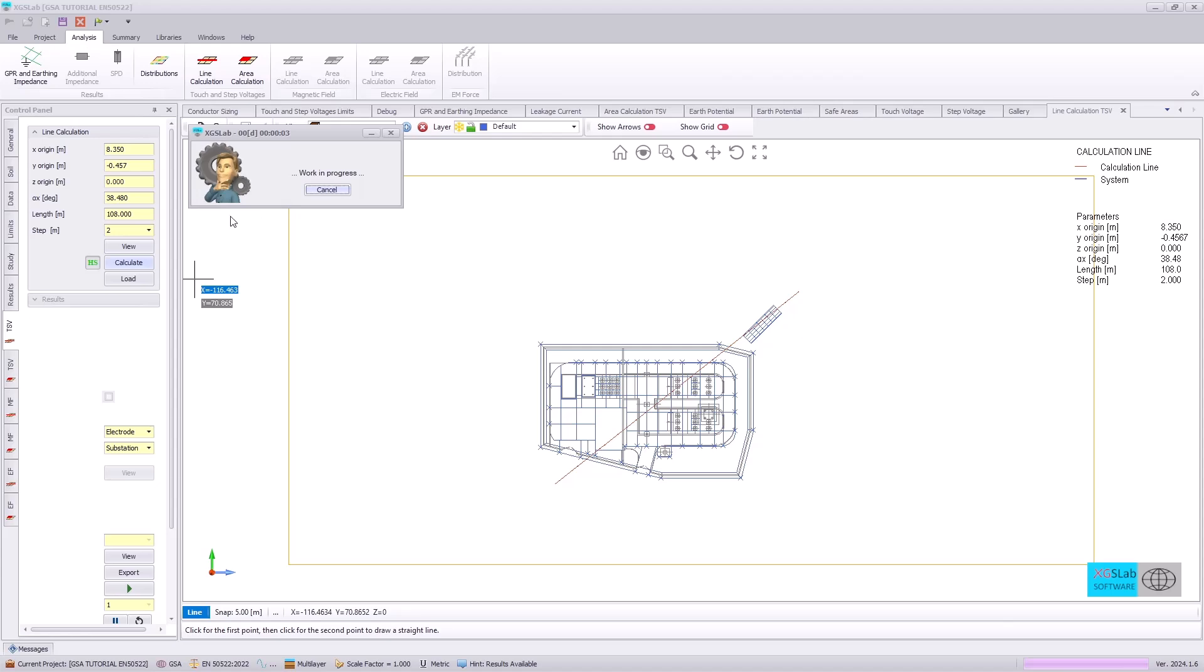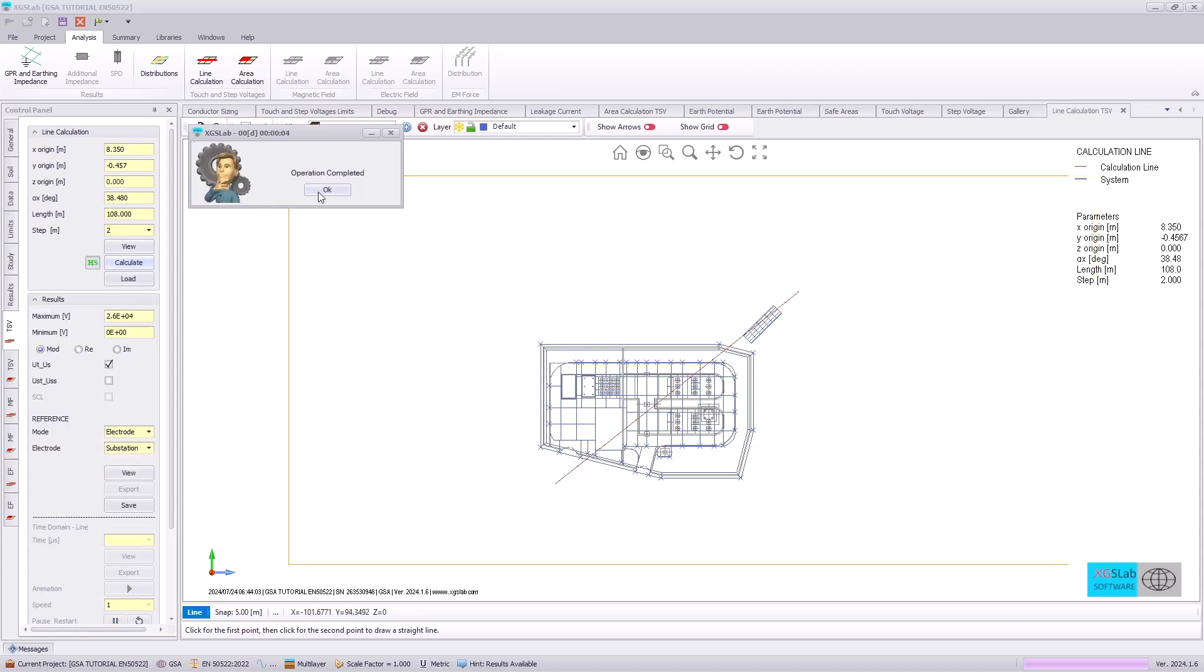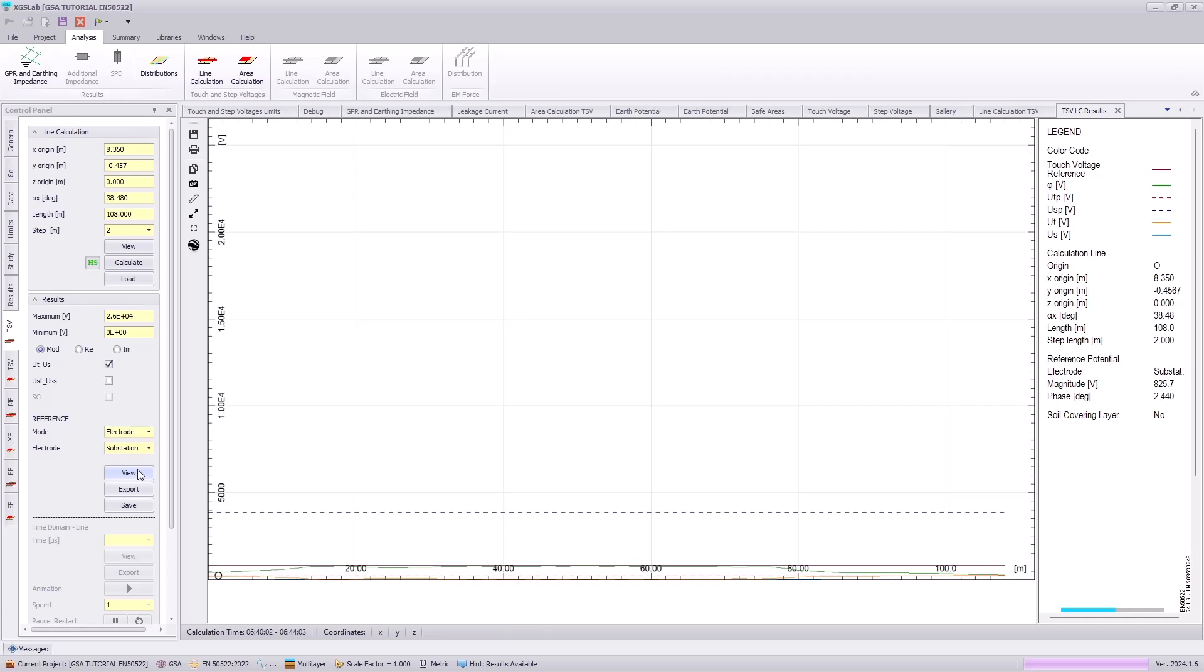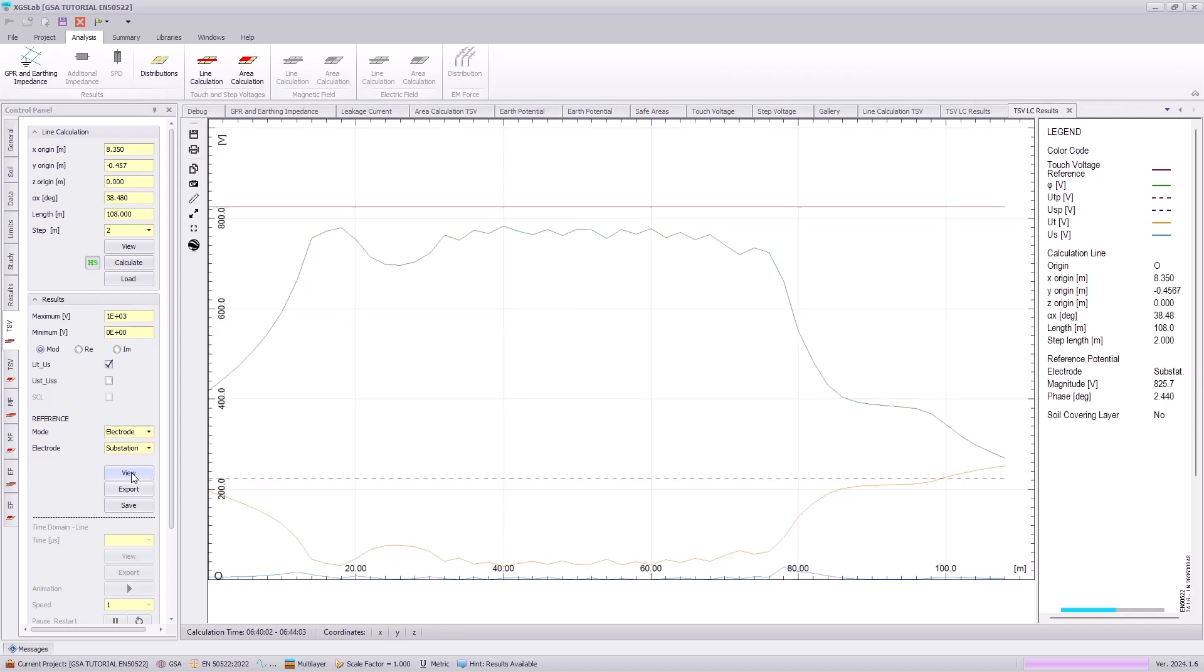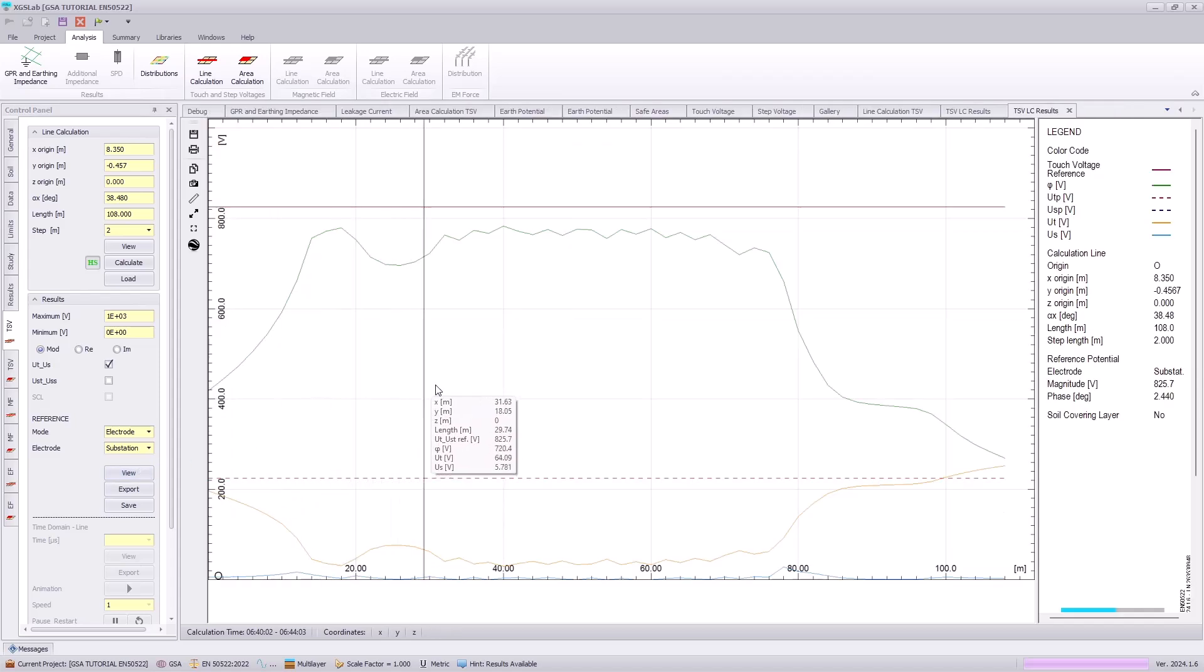And then we will need to specify the electrode reference as substation. And then we can plot our line calculation. Note our maximum threshold for touch voltages may be much higher, so we will need to scale our maximum values to be more visually illustrative.